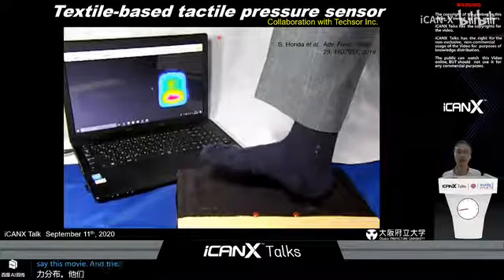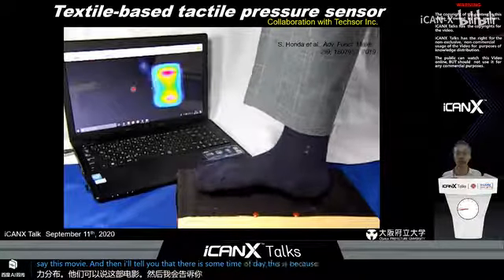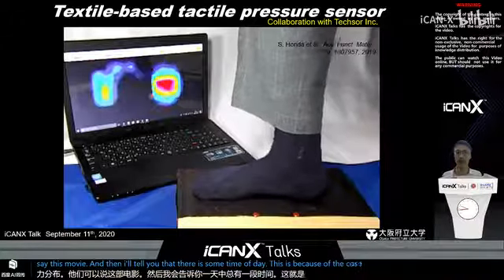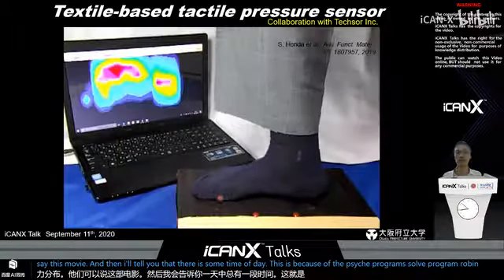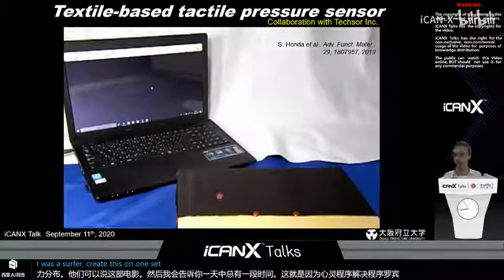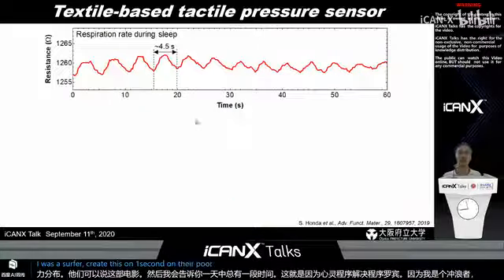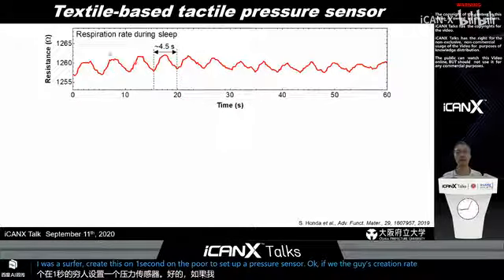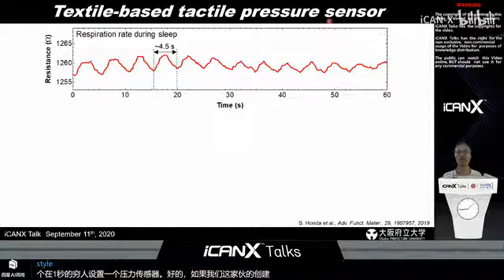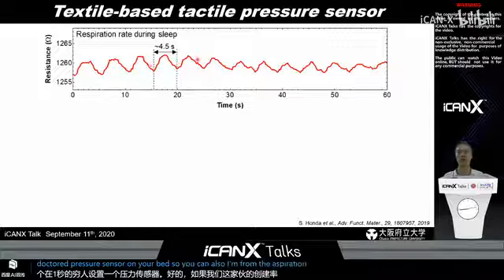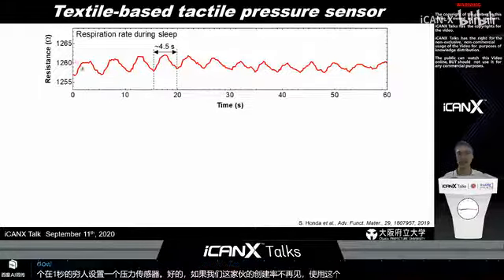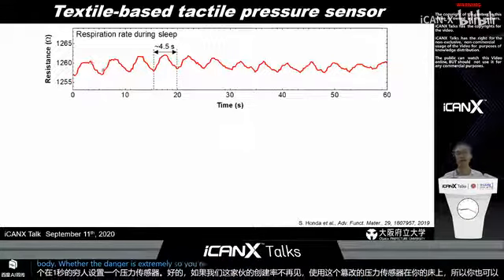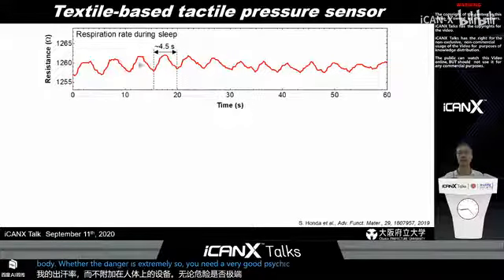And then actually there is some time delay. This is because of the circuit problem, the program problem. The sensor response itself is very quick, less than 1 second. And for this tactile pressure sensor, if we want to measure the respiration rate by using it on your bed, we can monitor the respiration rate without attaching the device onto the human body. However, the resistance change is extremely small, so you need a very good readout circuit if you want to do this respiration monitoring.